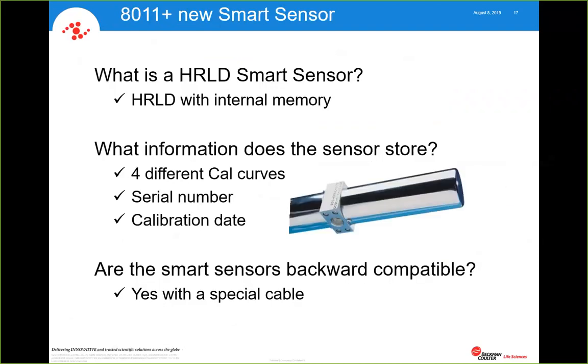Okay, so with 8011 Plus, we now have what we call a smart sensor. A smart sensor has the ability of storing up to 4 calibrations in the sensor itself. So if I were to take that sensor and calibrate it on one 8011 Plus system, and then I wanted to move that sensor over to another 8011 Plus system, it's a simple matter of reconnecting it, both fluid and electronically, and when you power it up, it uploads the calibration information from the sensor right into the system.